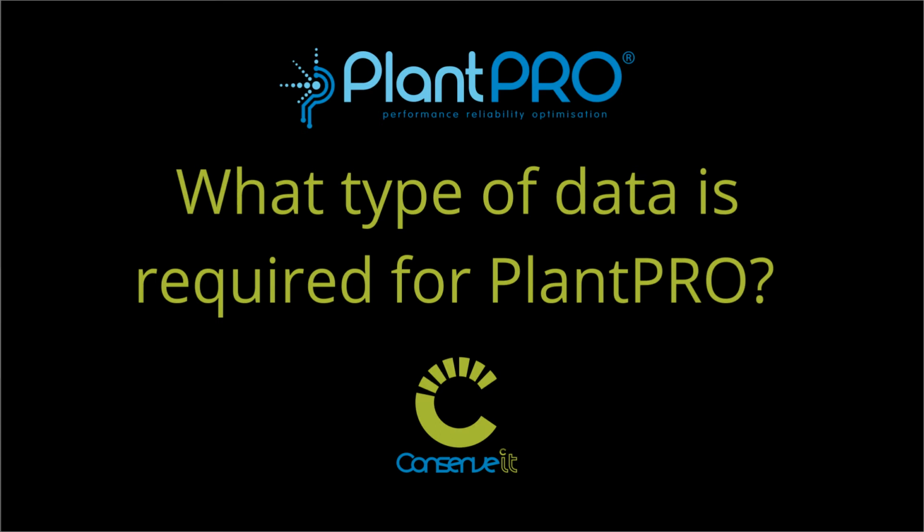What type of data is required for PlantPRO? PlantPRO needs a range of different sensor data inputs in order to make good data-driven decisions. Sensor data such as chilled water flow or differential pressure, chiller temperatures on the water side and on the refrigerant side, electrical information. For all pumps and cooling towers, we need status and VFD information, header, chilled water temperature and condenser water temperature. These are all important pieces of data for PlantPRO. The data should also be good, stable and accurate.